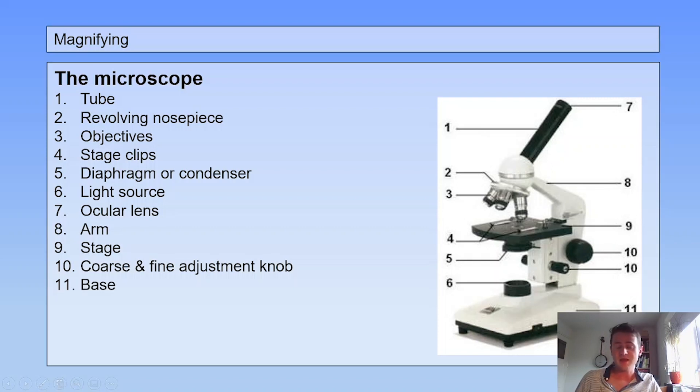And then 11 is the base. Now important: when you are transporting a microscope, so you're walking around with it, always carry it while you're holding number eight, the arm, and number 11, the base.